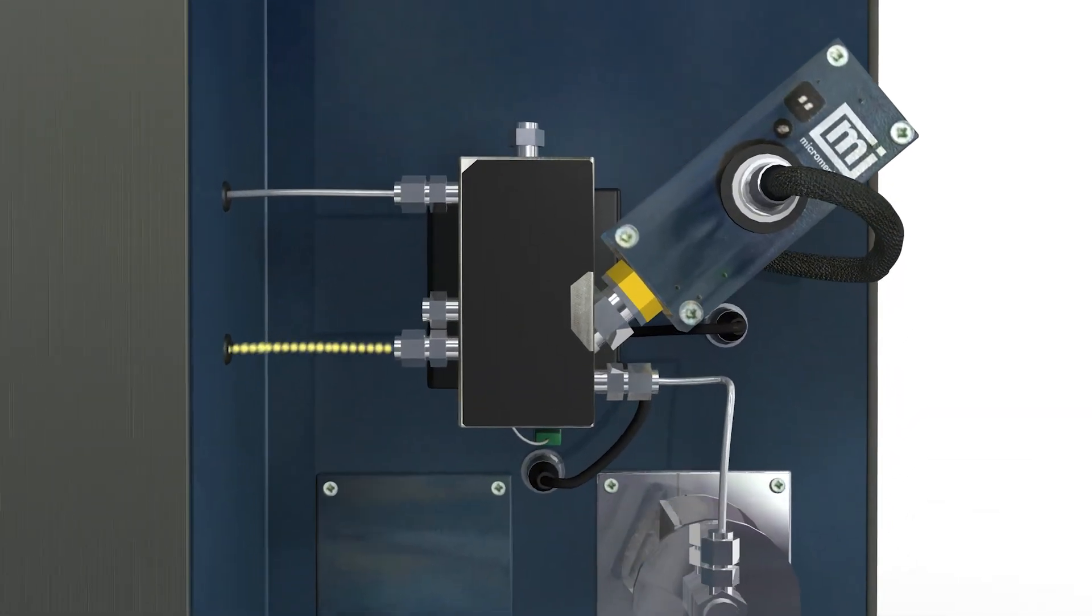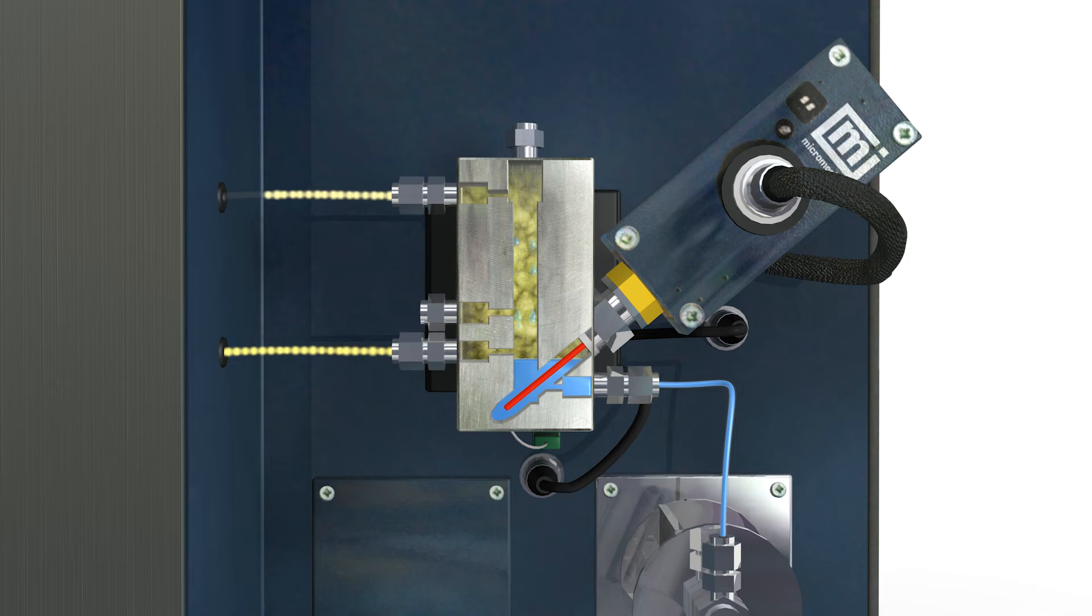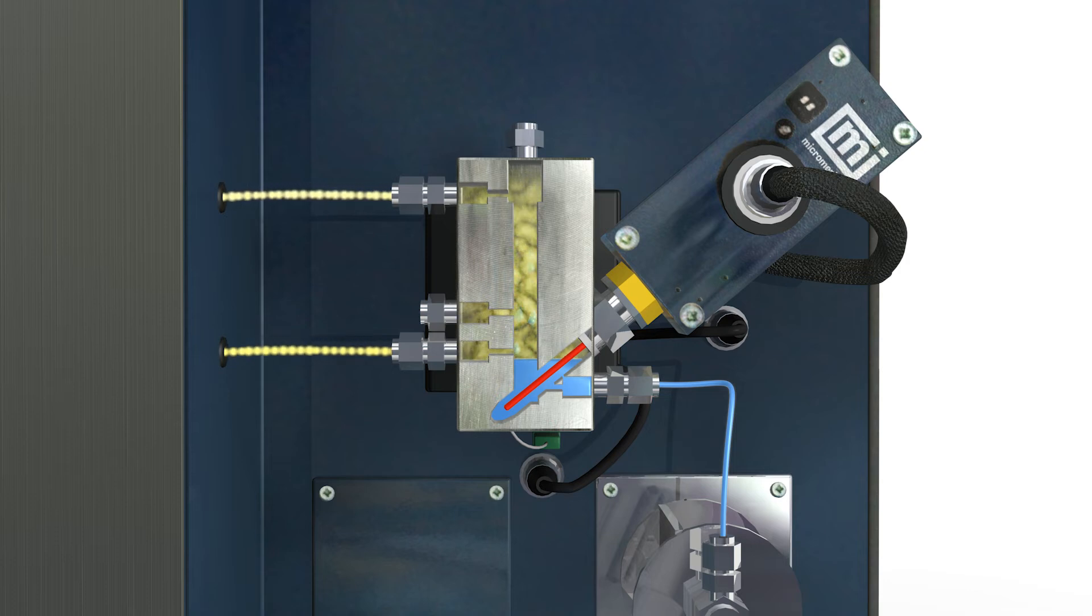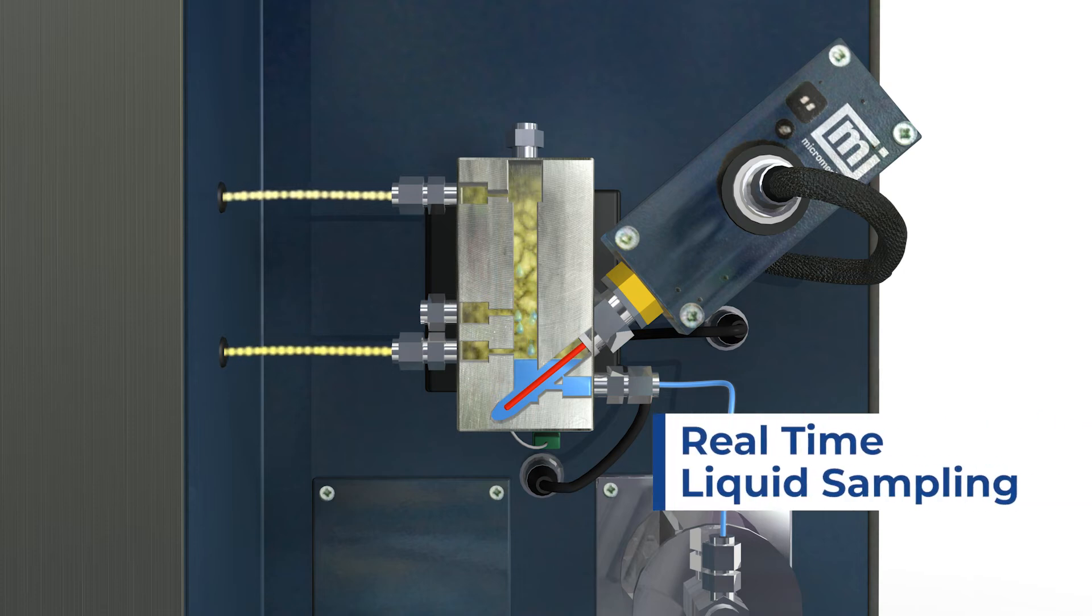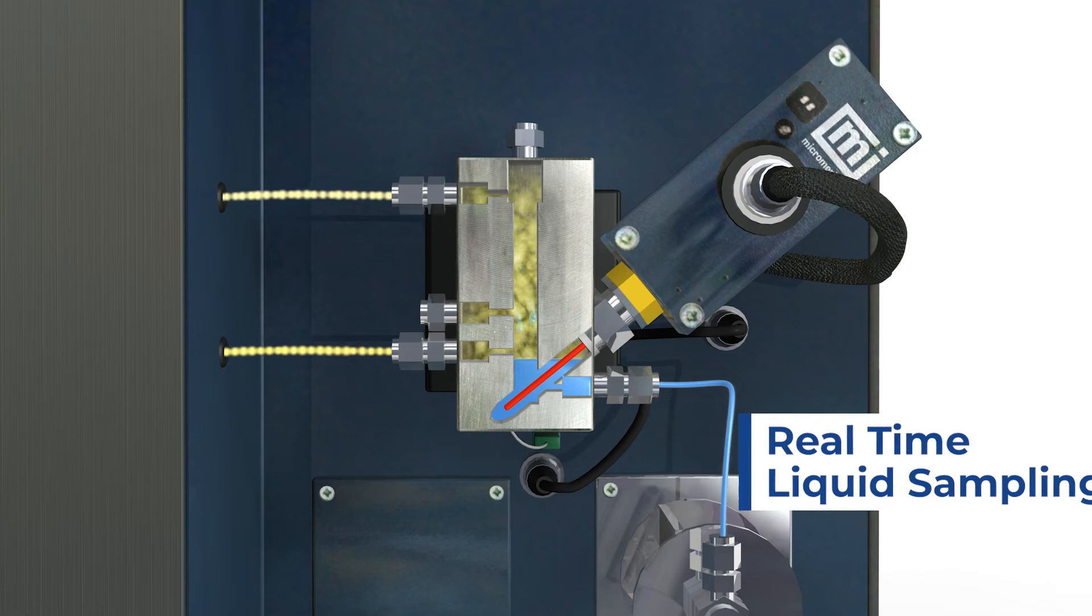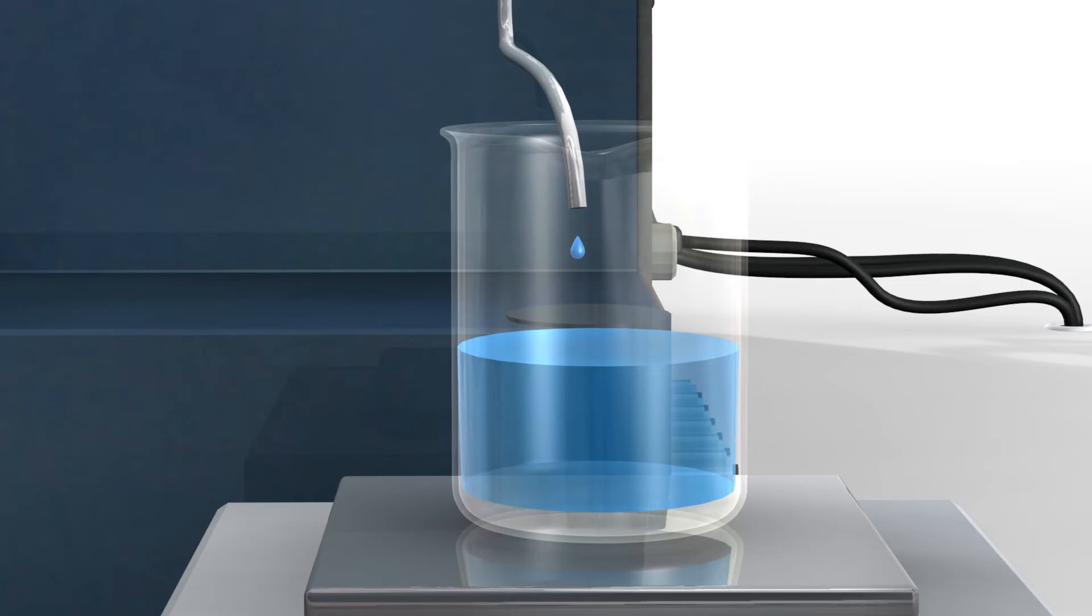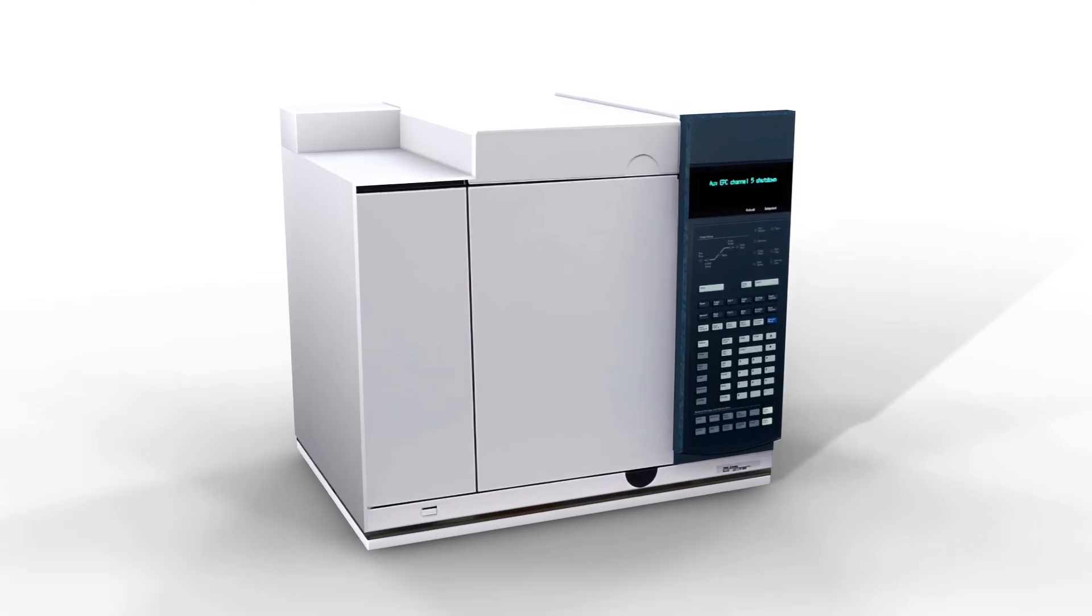A patented level control system keeps the volume in the separator constant. A minimal amount of condensed liquid from 0.5 milliliters is used to create a hydrostatic seal, allowing for liquid sample collection in real time, even at high pressures. The liquid mass is continuously recorded and available for mass balance calculations.